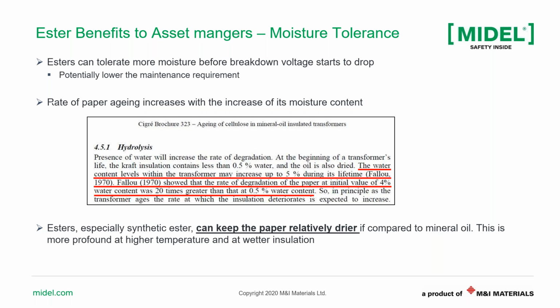Now, the part underlined in red indicates that a new transformer will have wet paper, usually only 0.5%, but then as it ages, the paper wetness will increase to 5%. With this increase, you can accelerate the aging rate of the paper, and so the asset will live shorter. What esters can contribute here is they can keep the moisture out of the paper, especially synthetic ester, and so keep the paper relatively drier. With a drier paper, the paper will live longer.